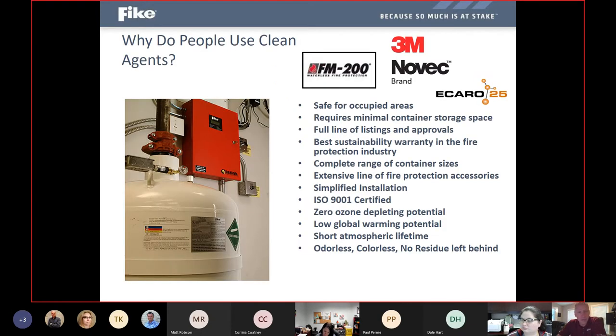All three of those, and why people use them, because all three of those are completely safe for occupied areas, are fully listed and approved with everybody that needs to approve any of this stuff. They're all very sustainable. They're all certified and have very low global warming potential and zero ozone depleting potential with relatively short atmospheric lifetimes. And again, they all fall under that category of being odorless, colorless, and leaving no residue behind.